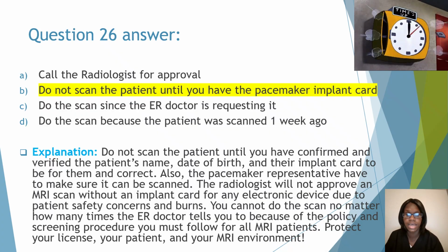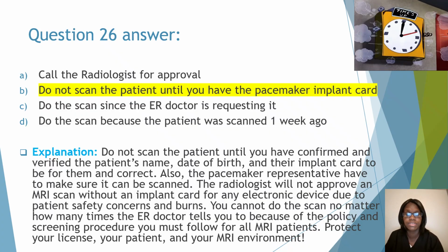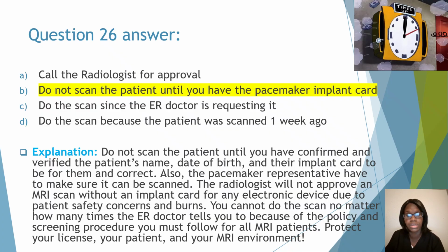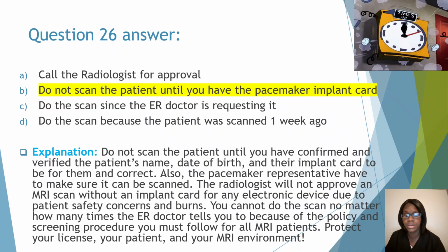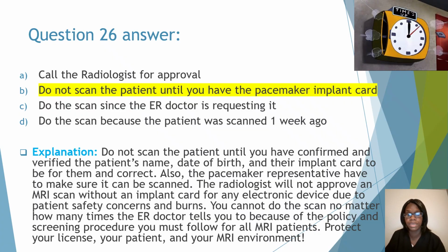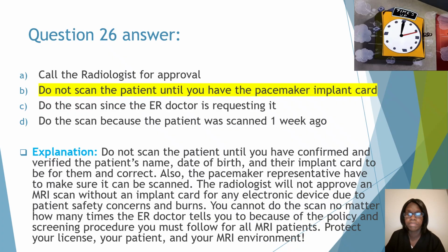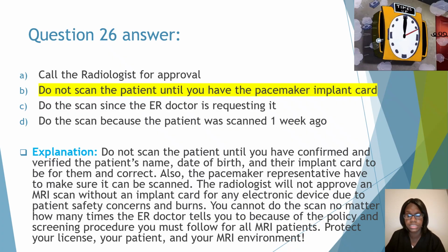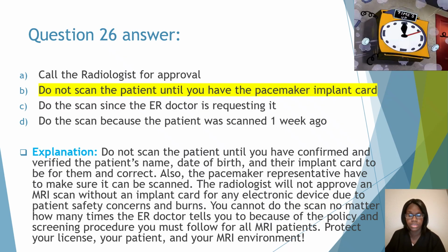And calling the radiologist really doesn't make a difference because they are not going to approve an MRI scan without an implant card anyway. So even though the ER doctor is being persistent and insisting that you do the scan, you can't, because you have to follow hospital policy and protocol, and that is to screen every patient. So I always tell people, protect your license, protect your patient, protect your MRI environment, because that's your suite. You're the one that has control over it.